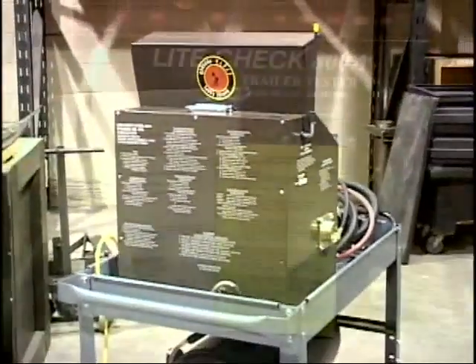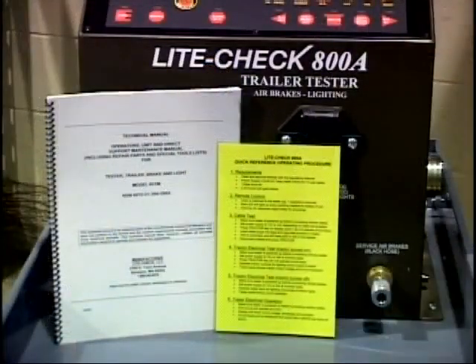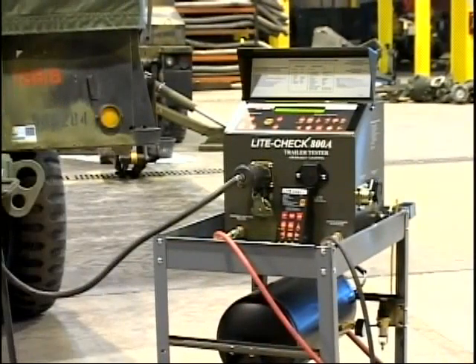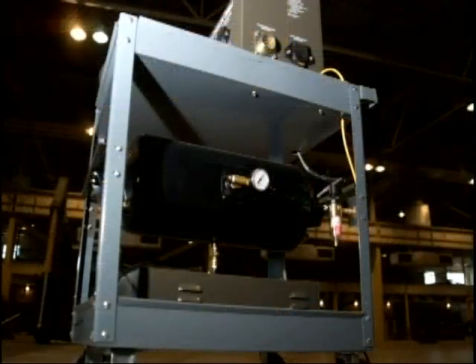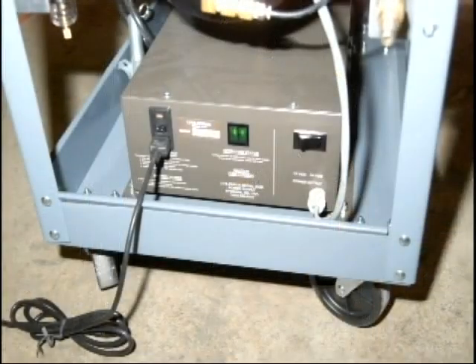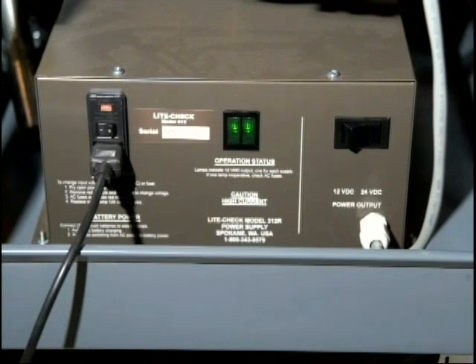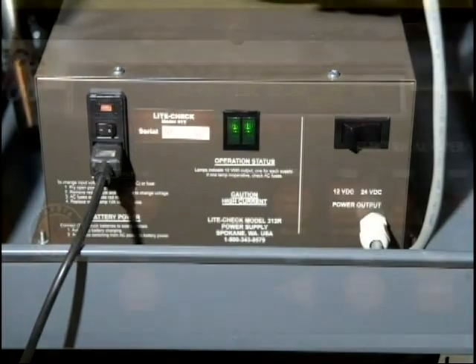Instructions are printed on the tester enclosure. A complete operations and service manual is supplied along with laminated quick reference instructions. The test station requires compressed air and 110 volt AC or 220 volt AC power for operation. The mechanic selects the output power of 12 volts or 24 volts with the rocker switch. An on-off switch is located in the power input module, which also includes fuses and allows a selection of 110 volts AC or 220 volts AC.